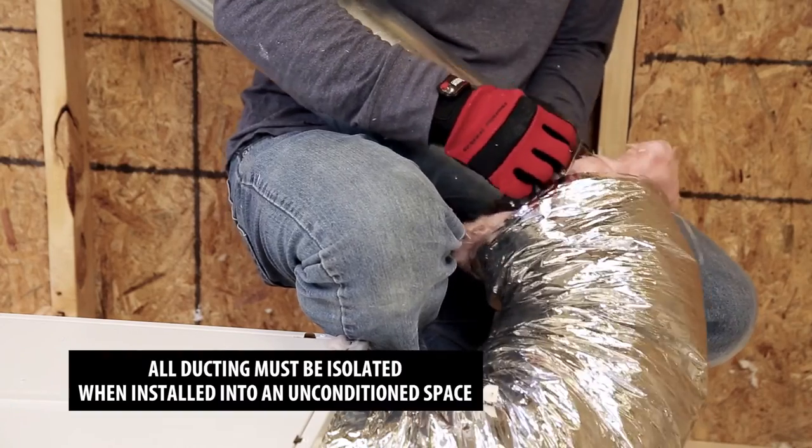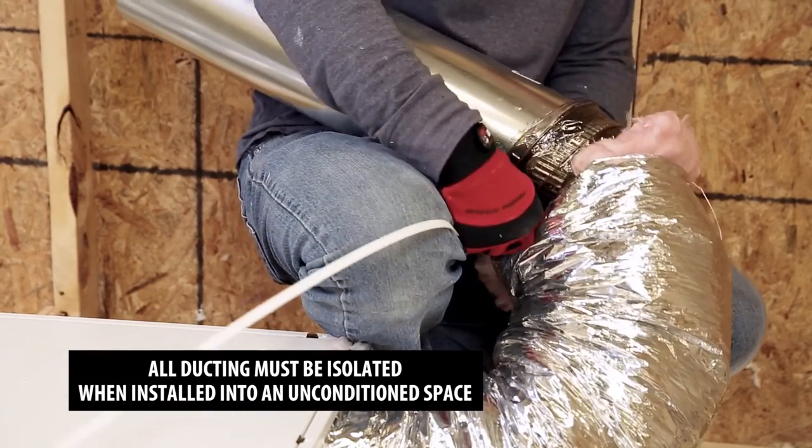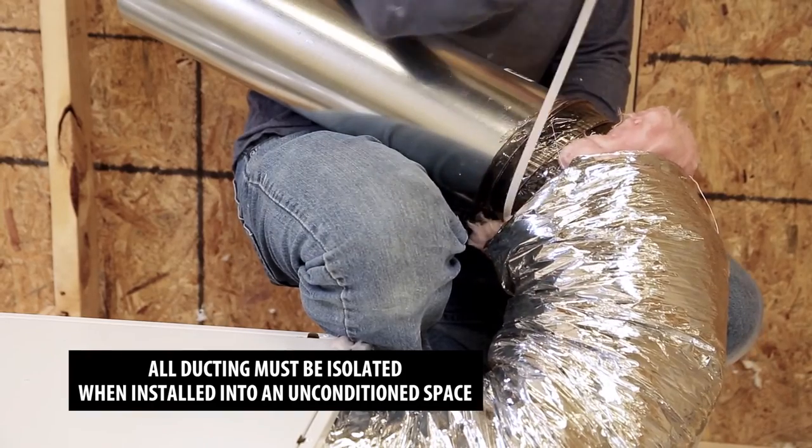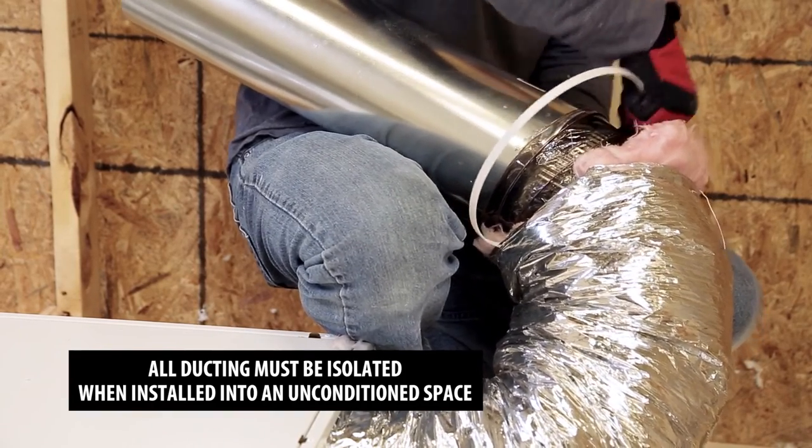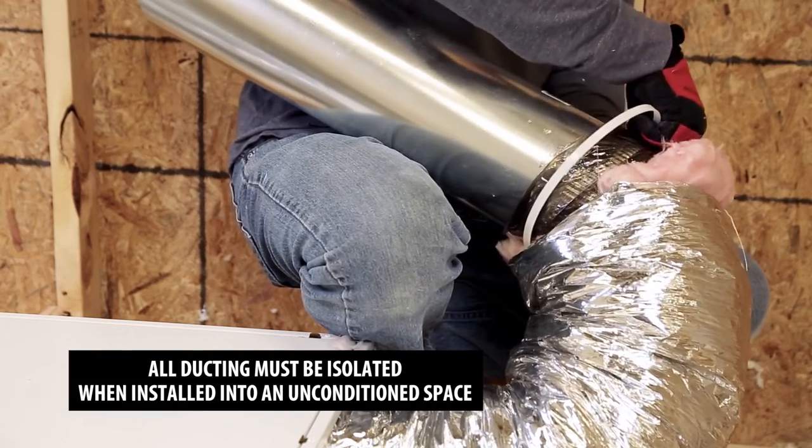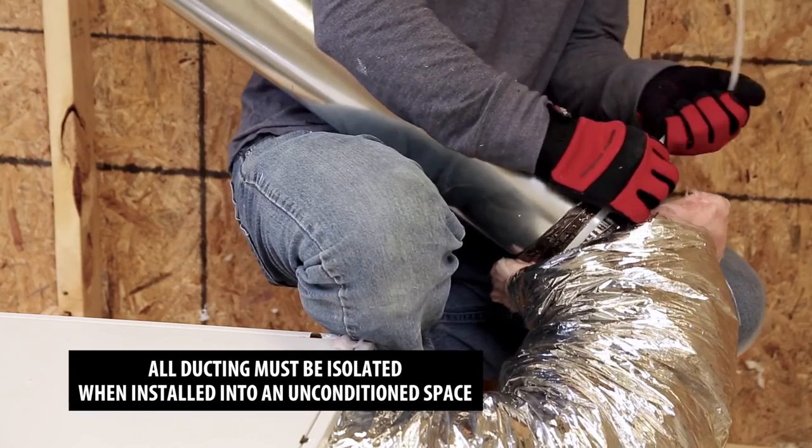Flexible ducting is recommended. If you must connect rigid ducting to the unit ports, use a section of flexible duct at least 6 inches long to avoid transmitting vibrations. Connect the flexible duct to the rigid duct using a tie wrap and foil tape. Never use screws to attach rigid ducting directly to the unit ports.